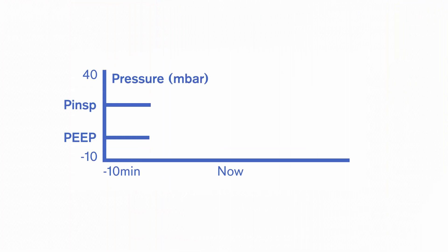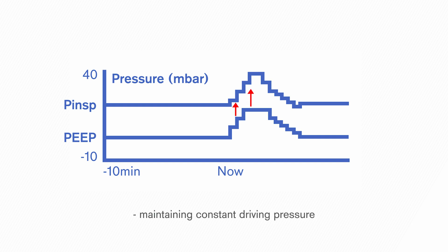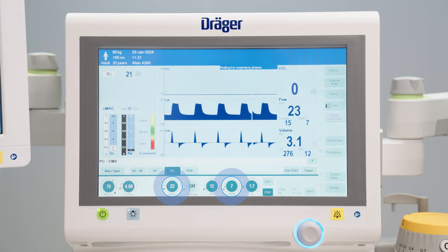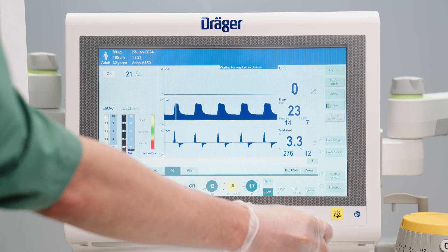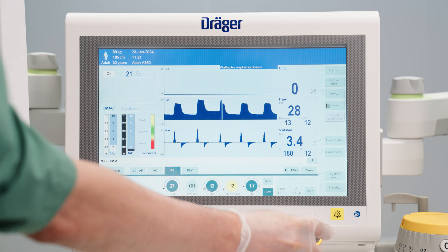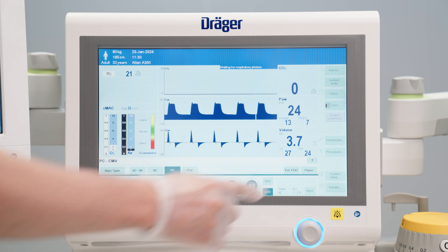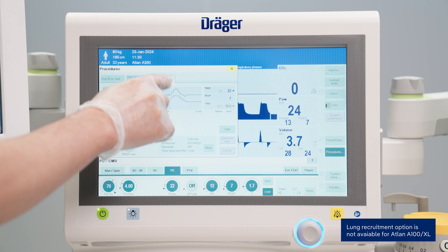The idea behind the multi-step recruitment manoeuvre, also known as incremental recruitment, is to carry out alveolar recruitment effectively and gently with respect to lung and hemodynamics. To do so, inspiratory pressure and PEEP are ideally increased step by step while maintaining a constant driving pressure. By linking PEEP and inspiratory pressure, Drager anaesthesia devices facilitate the manual implementation of these manoeuvres. After the alveolar opening pressure is maintained for the desired time, both inspiratory pressure and PEEP will be gradually decreased. Additionally, the Atlan family offers a procedure to automate the manual set-up effort for these kinds of time-consuming manoeuvres.